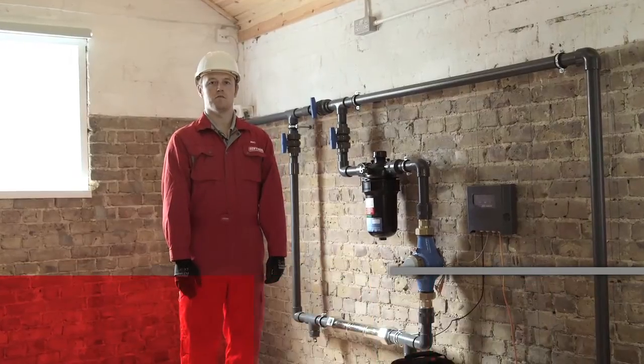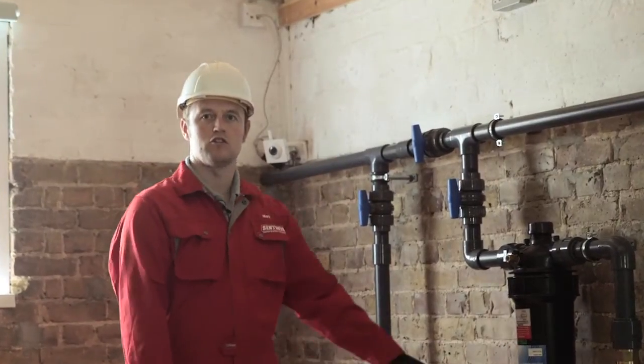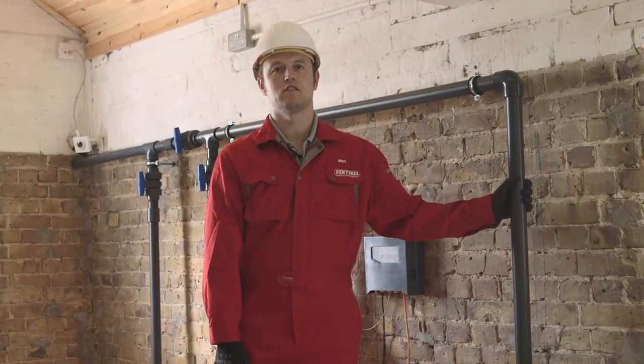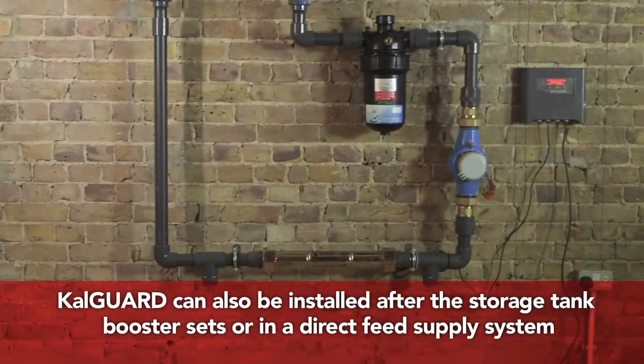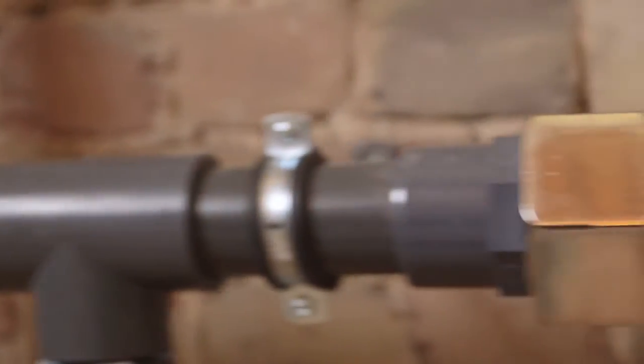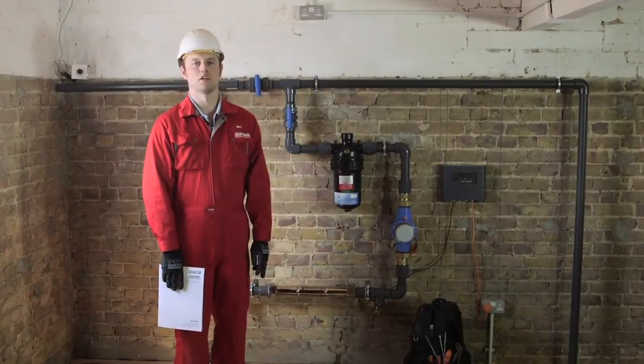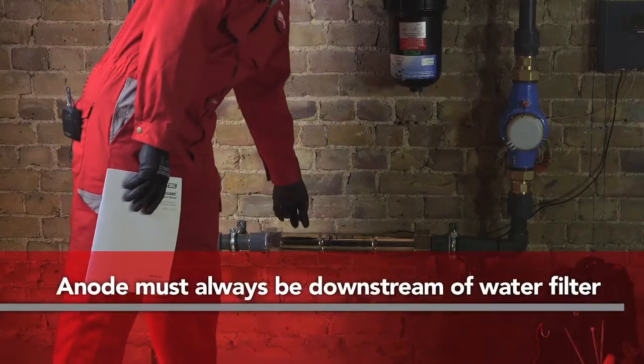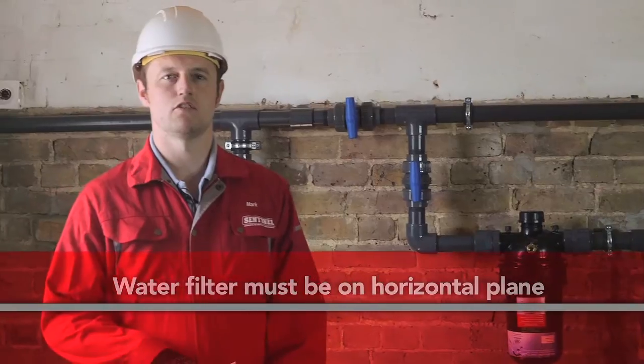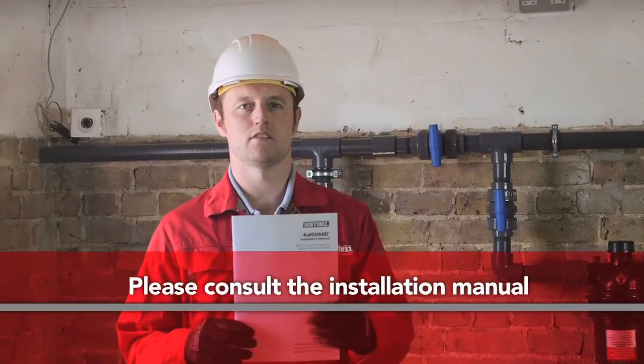KalGuard components must be installed in-line in a bypass or sidestream to the main water feed, and can provide whole system protection when installed on the rising main before cold water storage tanks. The system configuration can be adapted to suit the installation space available, but a few guidelines must be followed — for example, the anode must always be downstream of the filter, and the filter must always be on the horizontal plane. For detailed instructions, schematics, and a checklist, see the installation manual.